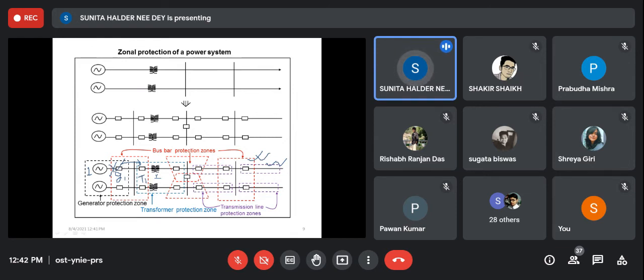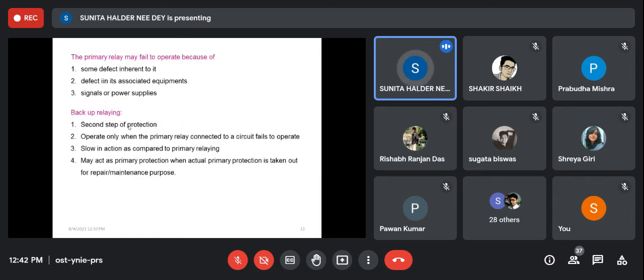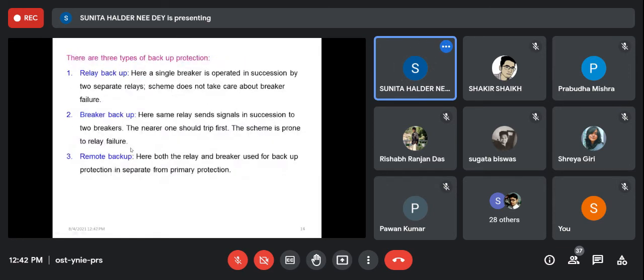So if there is a problem in the breaker in G1, then the T1 breaker will operate. But in that case, we are relying on the relay. If there may be a problem in the relay also, it is always better to take a separate set of relay. That is remote backup. The relay and breaker set is totally different from the primary relaying, for the backup relaying. So that is written here. Remote backup.